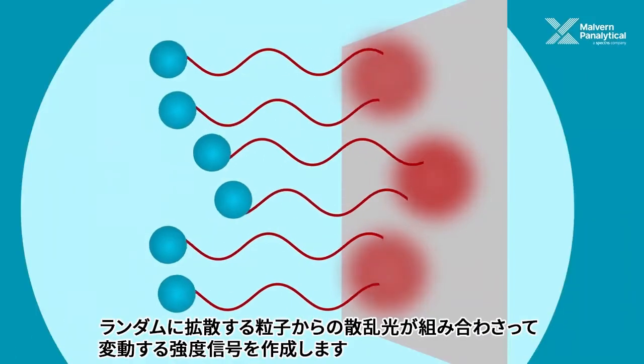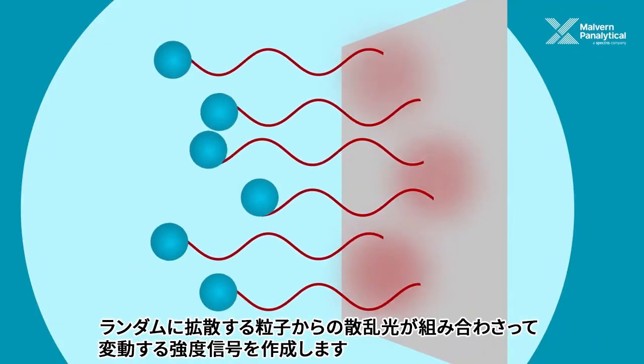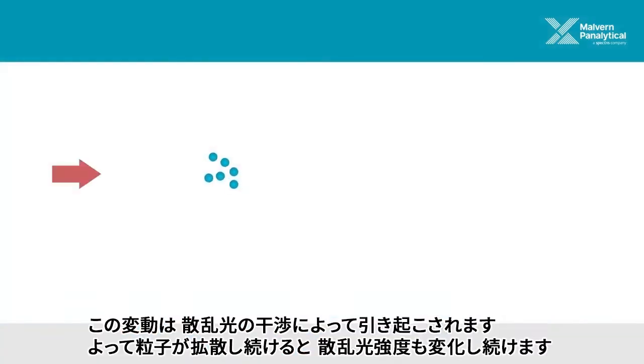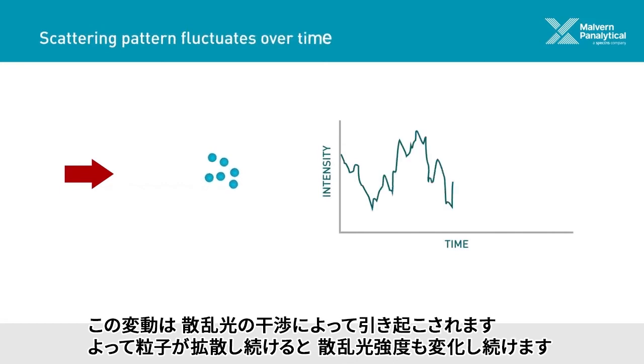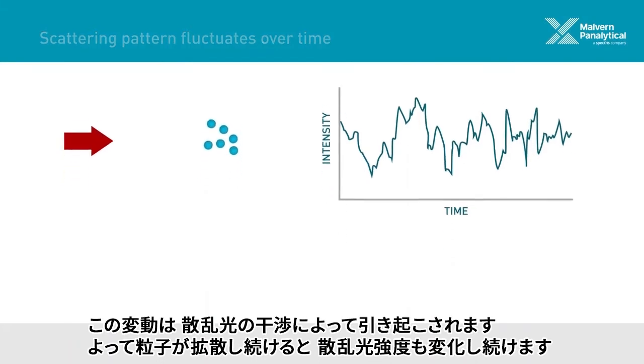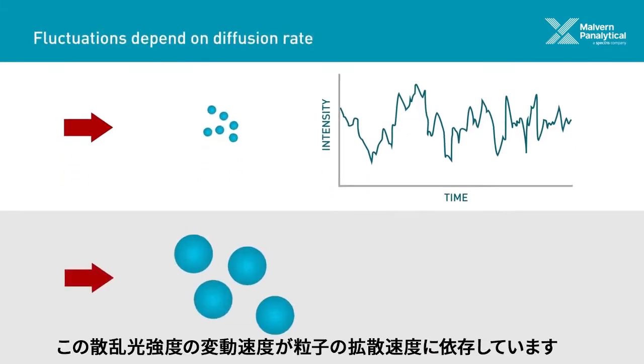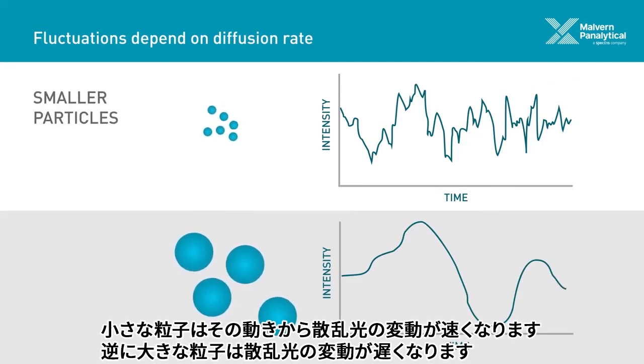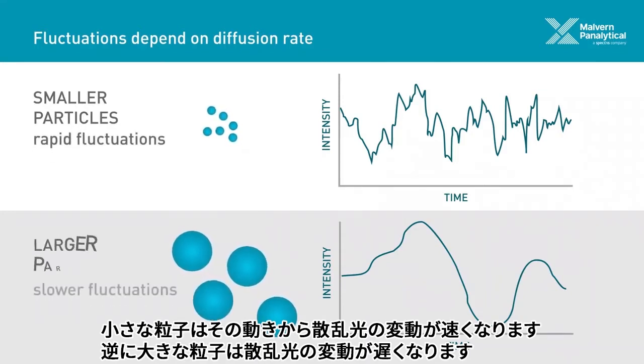The detected light scattered from lots of randomly diffusing particles combines to create a fluctuating intensity signal. The fluctuations are caused by the interference of light scattered by each individual particle, and the intensity will change over time as the particles continue to diffuse. The speed of these intensity fluctuations depends on the particle's diffusion rate — the smaller the particle, the more quickly it diffuses, which translates to more rapid fluctuations in scattered light, and vice versa.